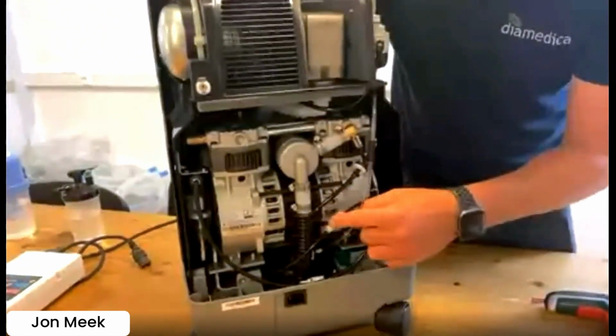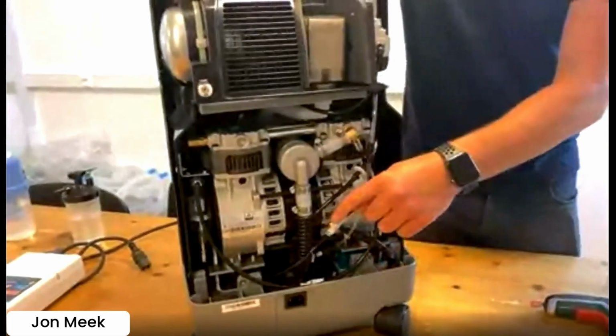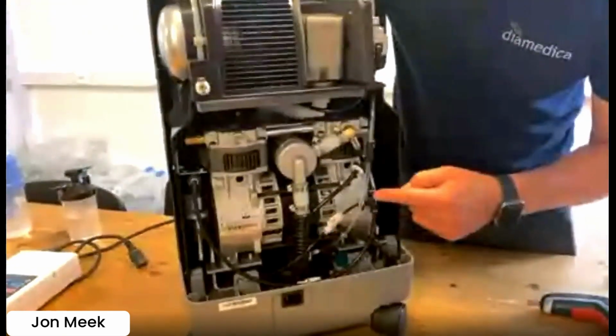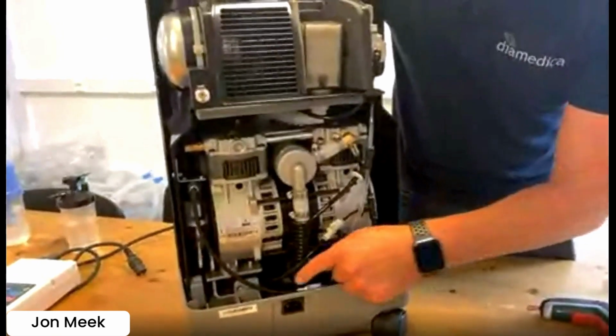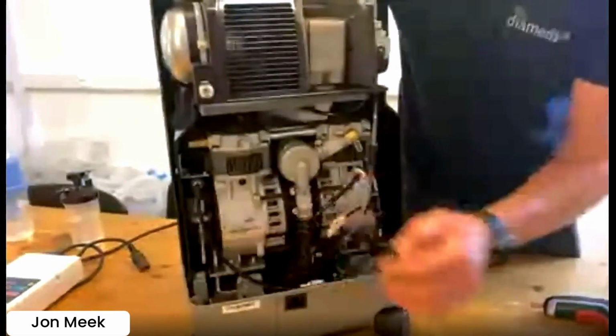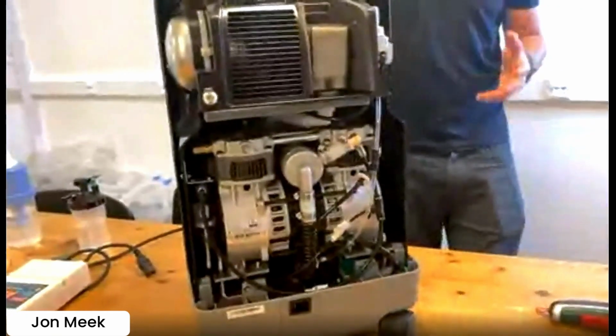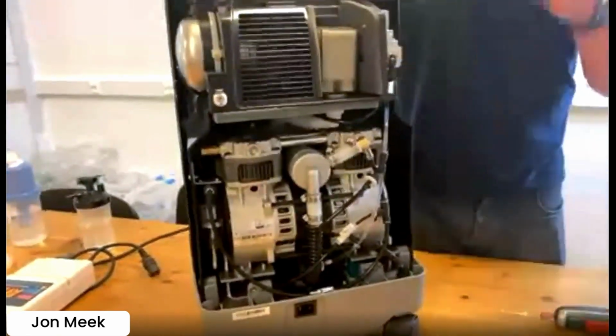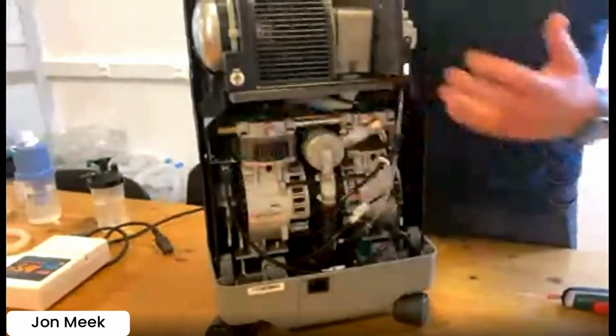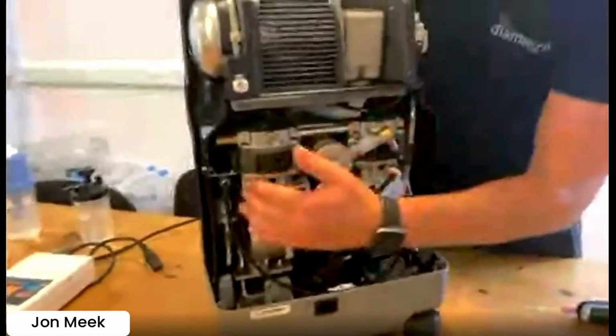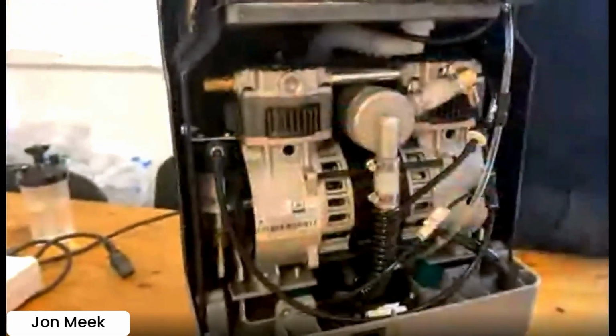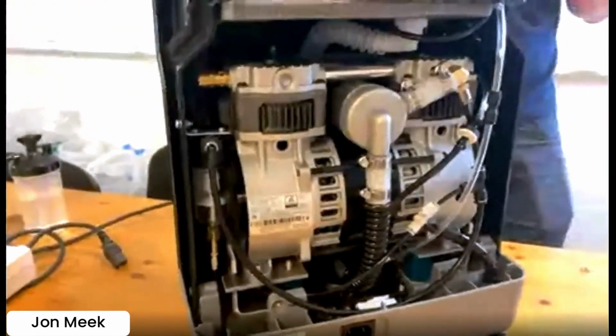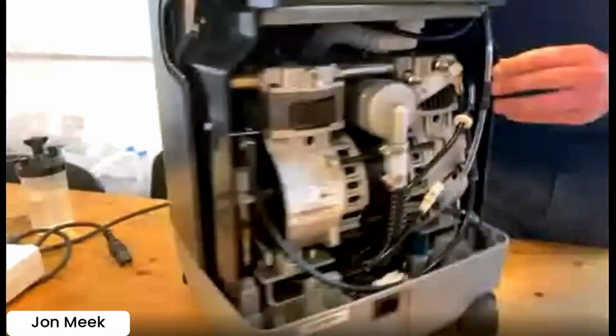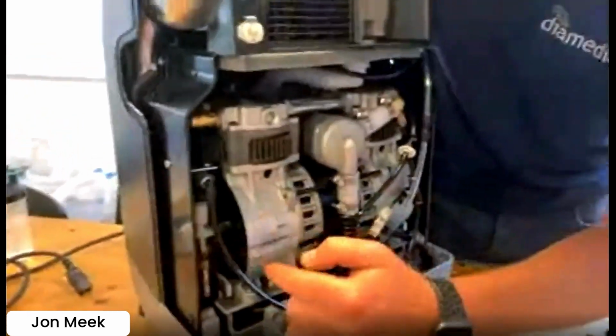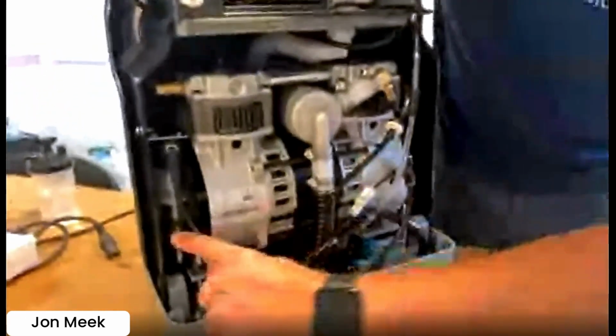And this allows a steady flow of warm air, warming it to the correct temperature. So this is set to no more than 6 litres a minute. So this is what we set this to. Coming off there, going down, like we had on the air set, it goes to a water trap. If you're trying to generate air from a compressor in environments of high humidity, you're going to get moisture in there. So it's really important. And these are self-draining water traps, like I said before. So they will fill up to the white disc.